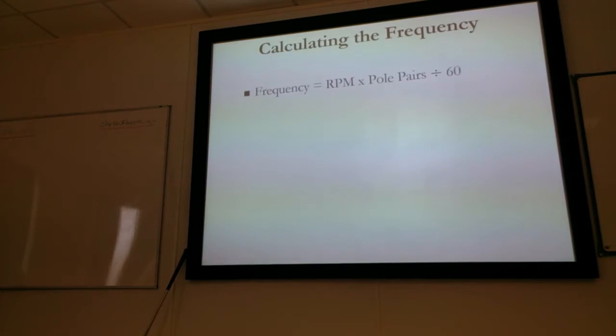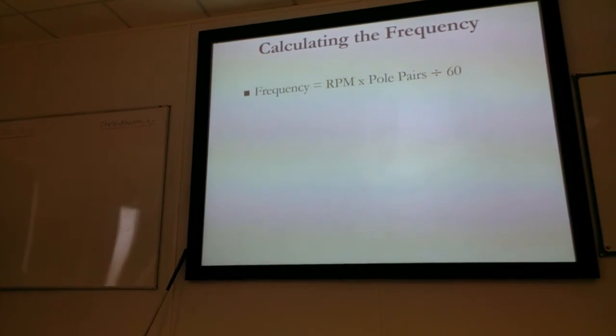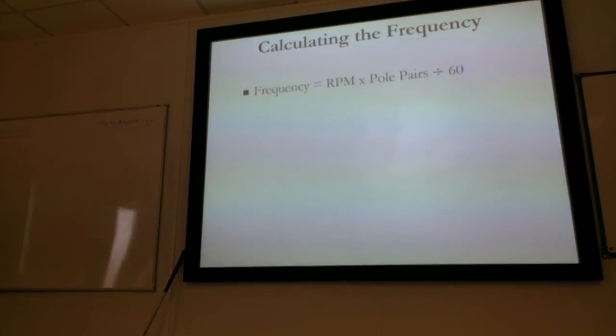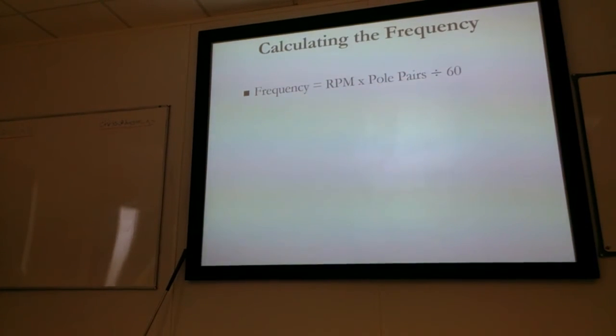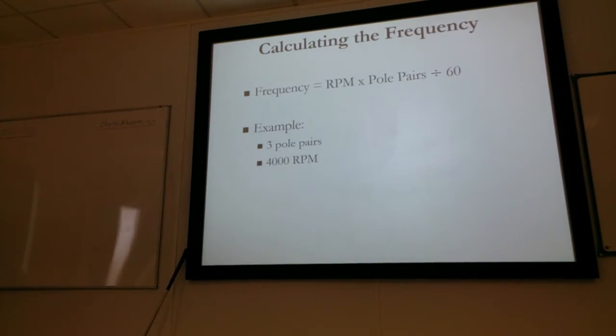Calculating the frequency is fairly straightforward. Frequency is equal to RPM times pole pairs over 60. The over 60 bit is just to get us from revolutions per minute to frequency per second, which is what we're after. For example, if we had 3 pole pairs turning at 4,000 RPM, what would be the frequency? What you got, Jim? You got your calculator out? 200. Yes. So 4,000 times 3 over 60 gives us 200 hertz. Yeah?